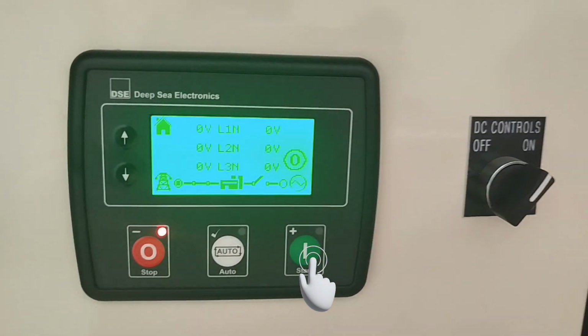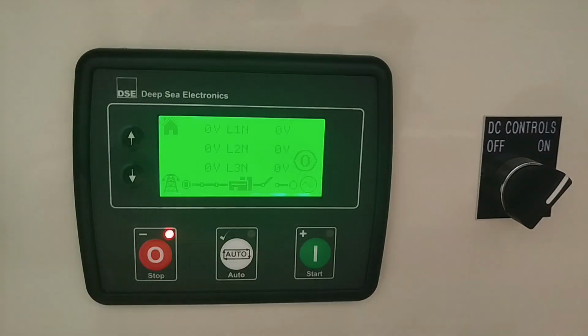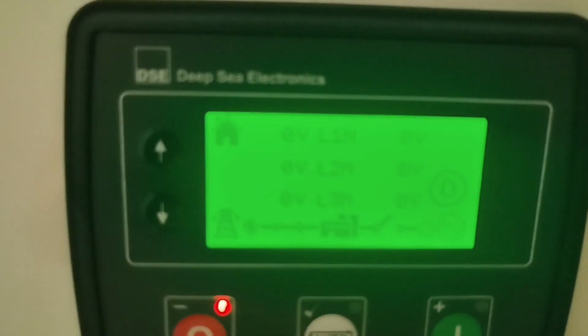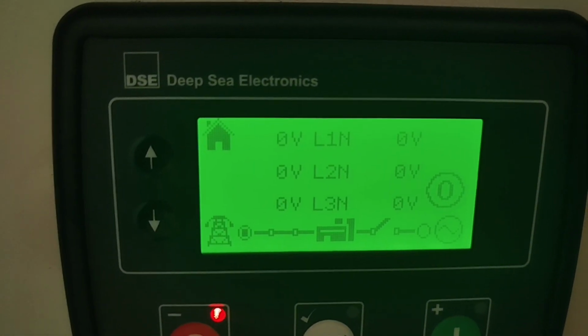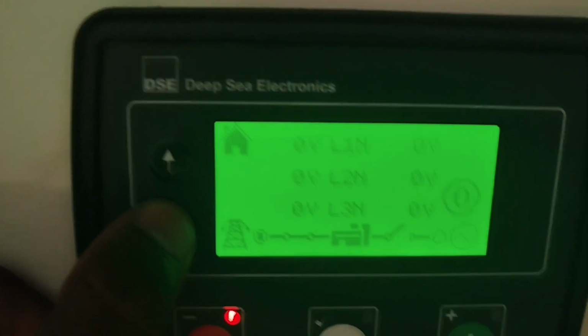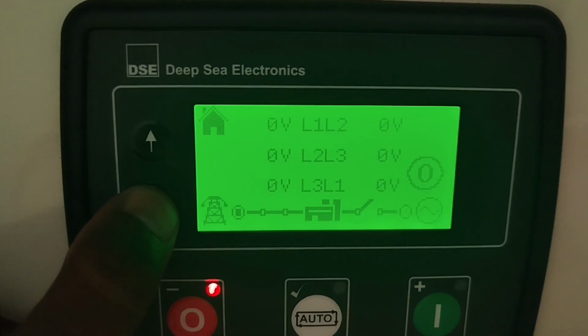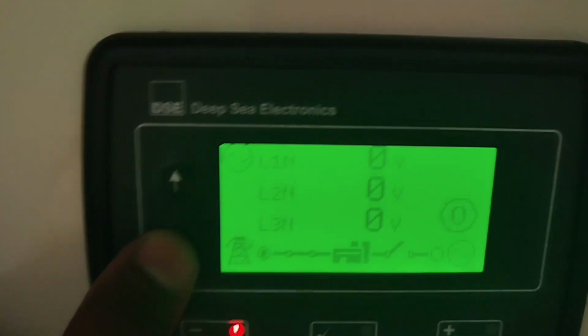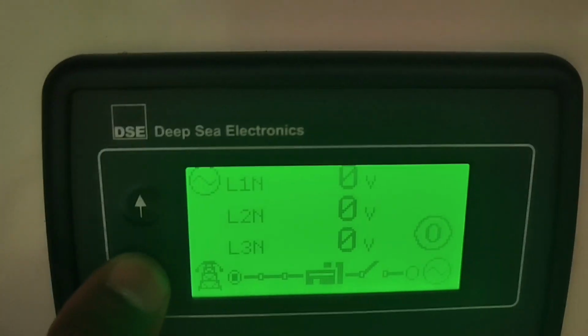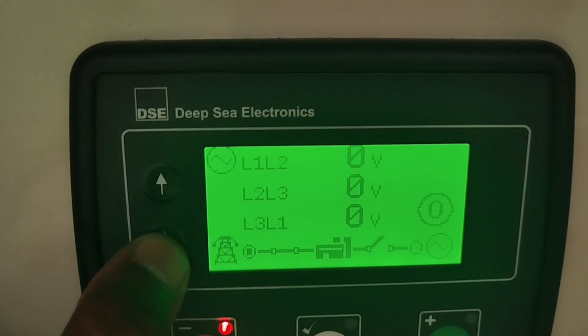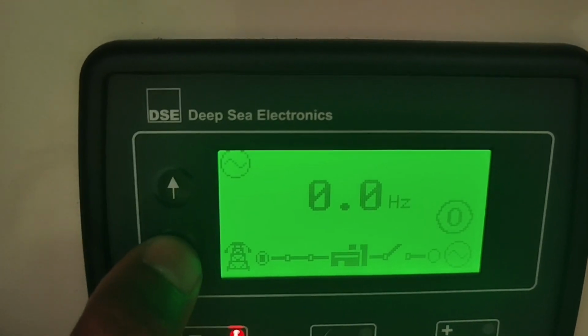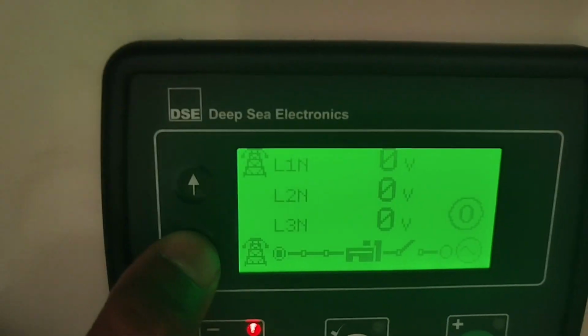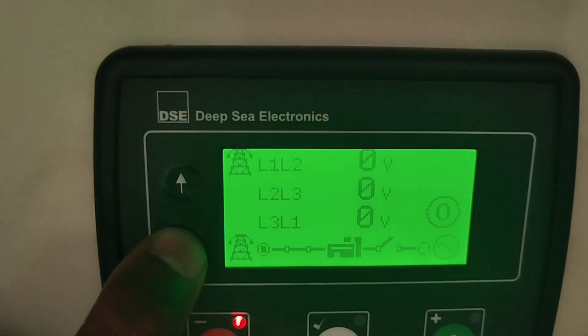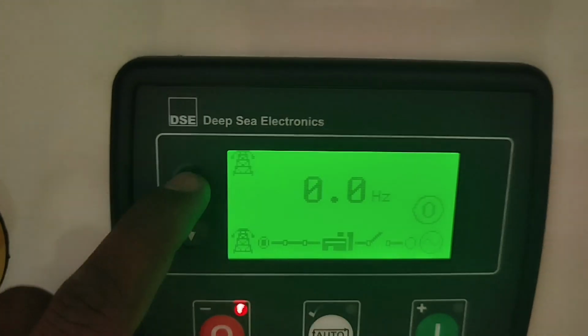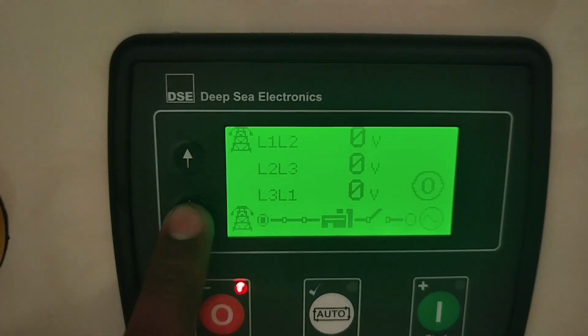Next we will guide you through all the controller parameters. This is the home page showing line to neutral voltages, and this is line to line voltages. This is the line to neutral generator voltages, and this is the line to line generator voltages, and this is the generator frequency. If you connect mains, this shows the line to neutral main voltages and line to line main voltages, and the frequency of the mains.